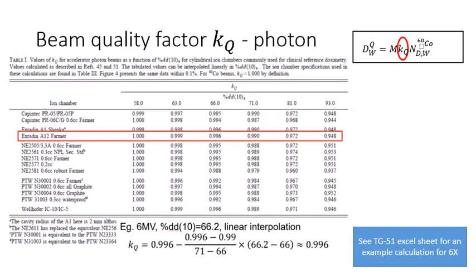As we said, we need to obtain the percentage depth dose at 10 cm to begin with. So for example, for a 6MV beam, we obtain this PDD at 10 equals 66.2 from the scan PDD data.